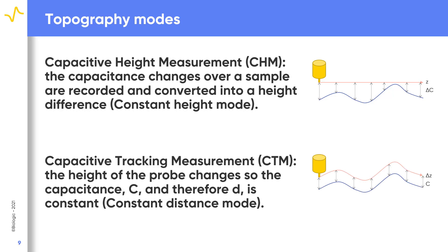Capacitive tracking measurement, or CTM, is the second measurement option. In this constant distance technique, the probe-to-sample distance is maintained throughout the measurement by moving the probe in Z to maintain the measured capacitance. In this case, the probe position is plotted throughout the measurement to map the sample topography. CTM is particularly useful for non-flat samples, for example curved pieces. However, because the probe position changes throughout the experiment, CTM measurements are slower than CHM measurements.